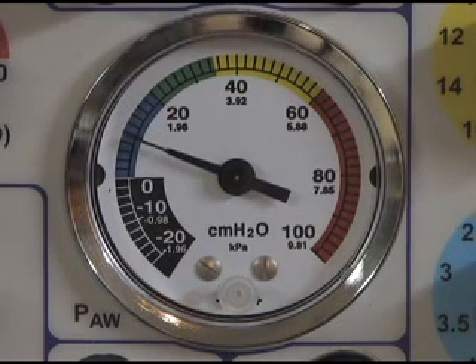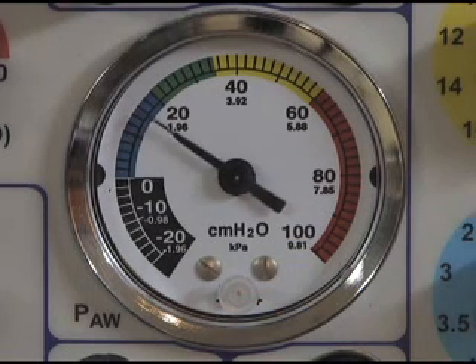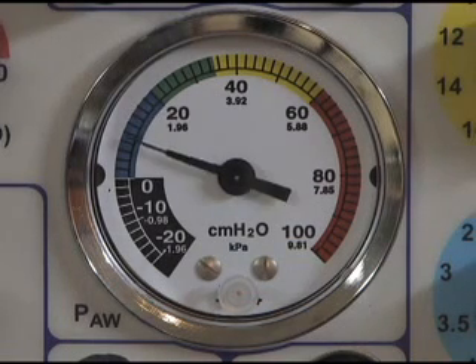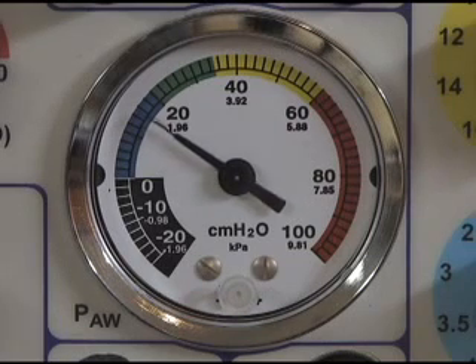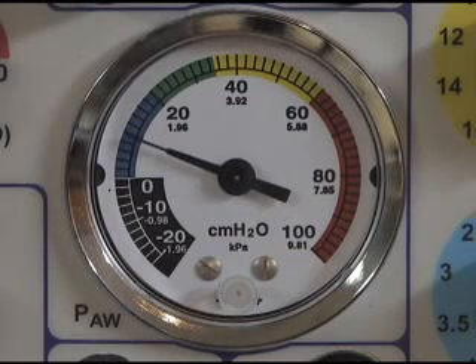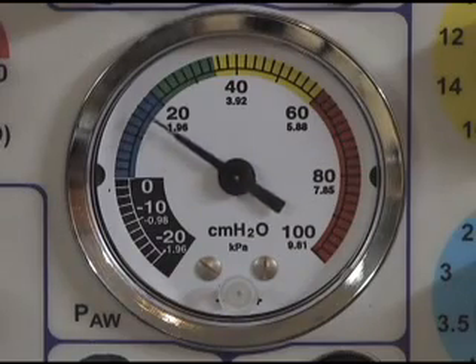In the PEEP mode, the flow of gas is shut off during the inspiratory phase so as not to add to the delivered tidal volume. Observation of the changing baseline pressure level on the airway pressure gauge will indicate that the CPAP PEEP control is functioning correctly. The spontaneously breathing patient can be supplied with CPAP PEEP, often eliminating the need for intubation.